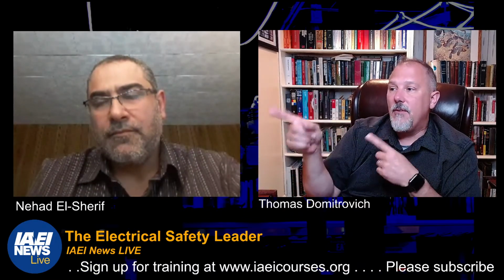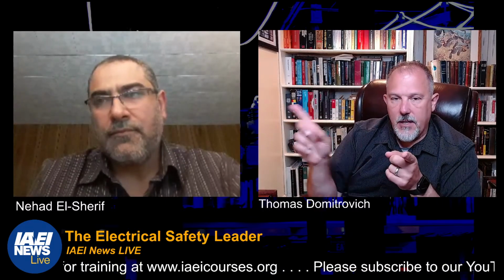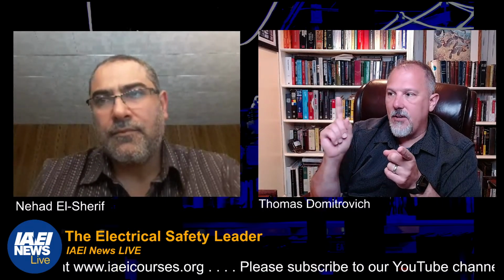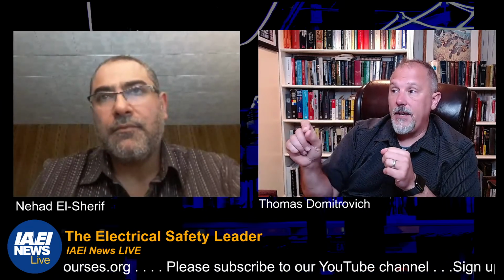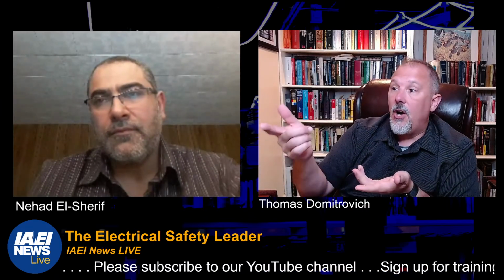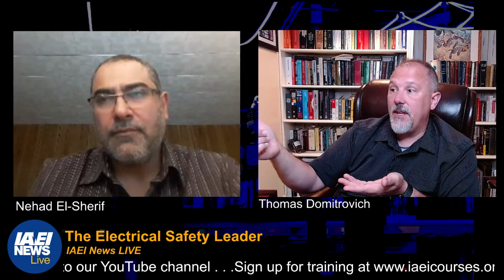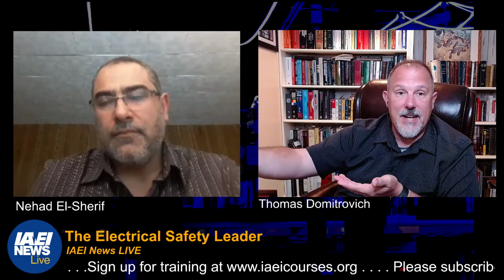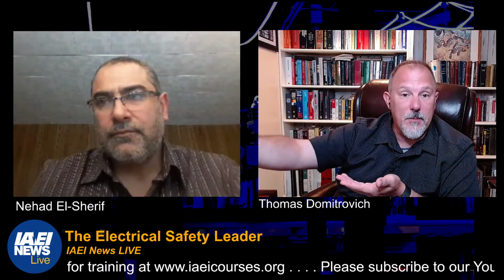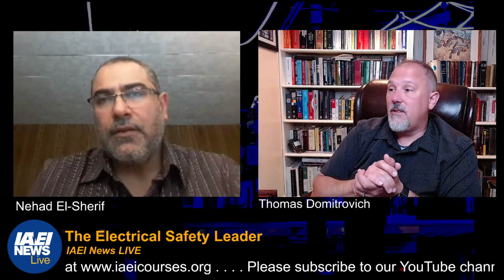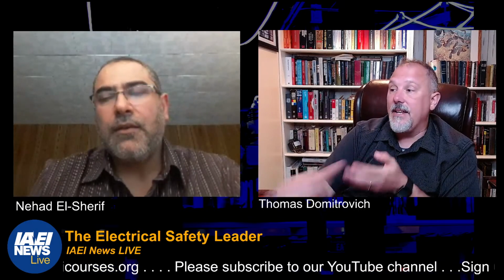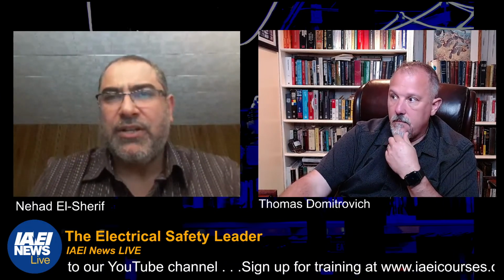The only area I see, because somebody brought this up to me, where there's some confusion with the language is where it says, for example, all receptacles rated 125 through 250 volts, 50 amps or less shall be afforded GFCI or a special purpose GFCI. Well, you couldn't put a special purpose GFCI on those receptacles because special purpose is above 250. So I think the language can be cleaned up a little bit, but I don't think it's a problem. You can get a Class C that is less than 150 volts, like I mentioned in the chart.